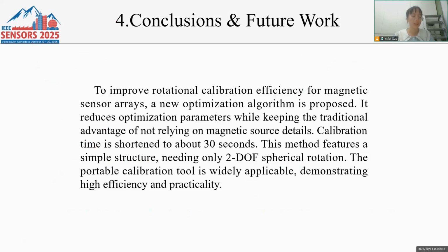To wrap up our magnetic sensor array calibration work, our main goal was to make rotational calibration more efficient, so we proposed a new optimization algorithm. What makes it stand out? First, it reduced the number of optimization parameters. Crucially, it still keeps the traditional method's key advantage: no need for detailed magnetic source info. That's a big plus, as it avoids the hassle of remeasuring or knowing every source detail. In performance, we've shortened calibration time to around 30 seconds, a significant improvement over longer processes.